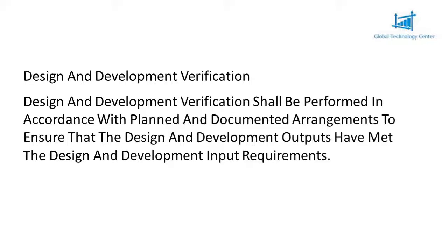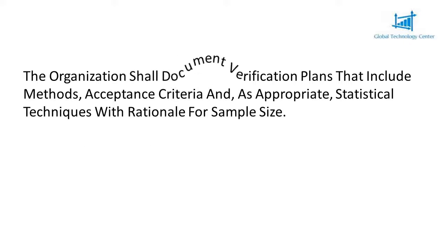Design verification shall be performed in accordance with planned and documented arrangements to ensure that the design outputs have met the design input requirements. The organization shall document verification plans that include methods, acceptance criteria and, as appropriate, statistical techniques with rationale for sample size.